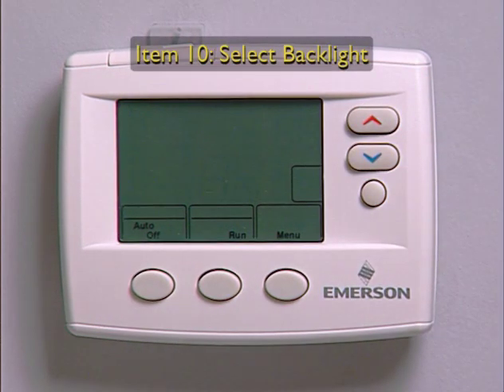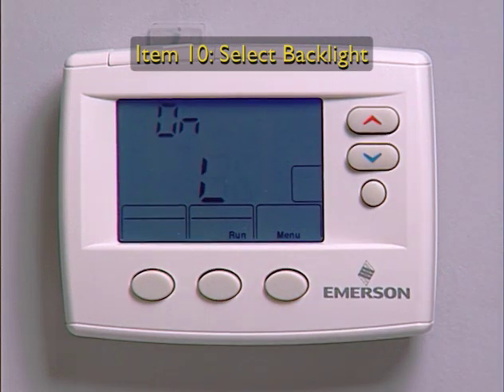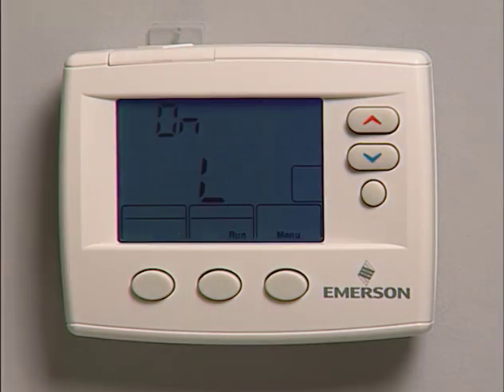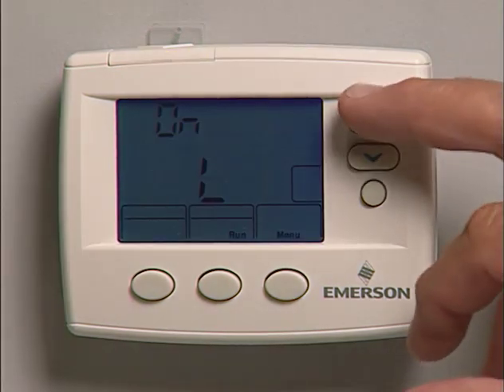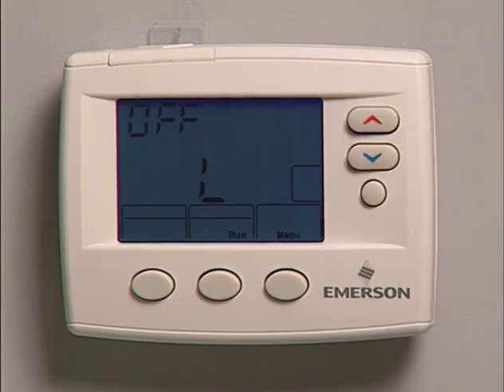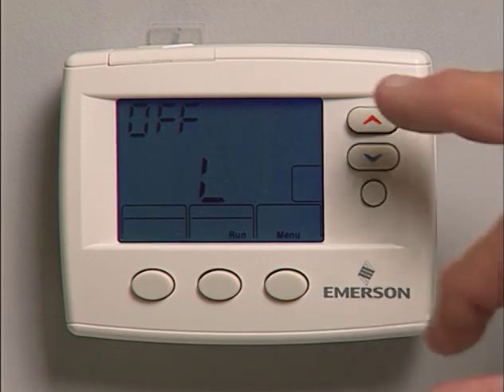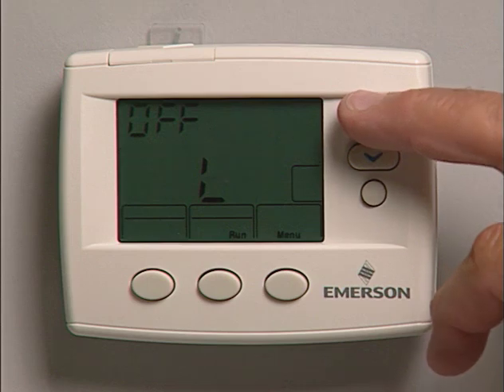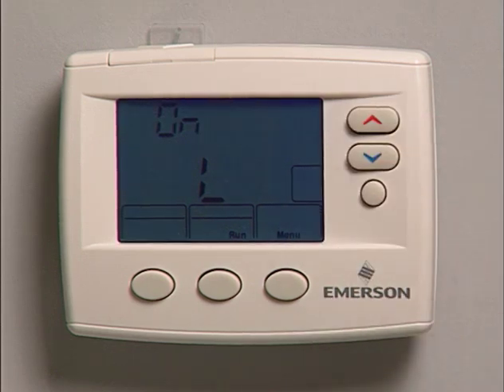Configuration menu option 10 is select backlight display, displayed as on L. This option keeps the light on continuously when the C terminal is powered. Selecting OFF L keeps the light on momentarily after a key is pressed. When the C terminal is not powered, the light goes on momentarily after a key is pressed no matter which option you select. For continuous backlight illumination, you must have the C terminal hooked up with 24 volts AC continuous.